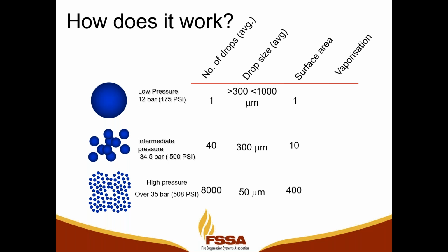And then, from a vaporization standpoint, the different sizes of droplets that you have are actually going to determine how readily those droplets are going to vaporize into basically steam, which creates a local inerted atmosphere at the fire core. So the faster the droplet evaporates into steam is going to determine how quickly it starts its firefighting principles. Next slide.